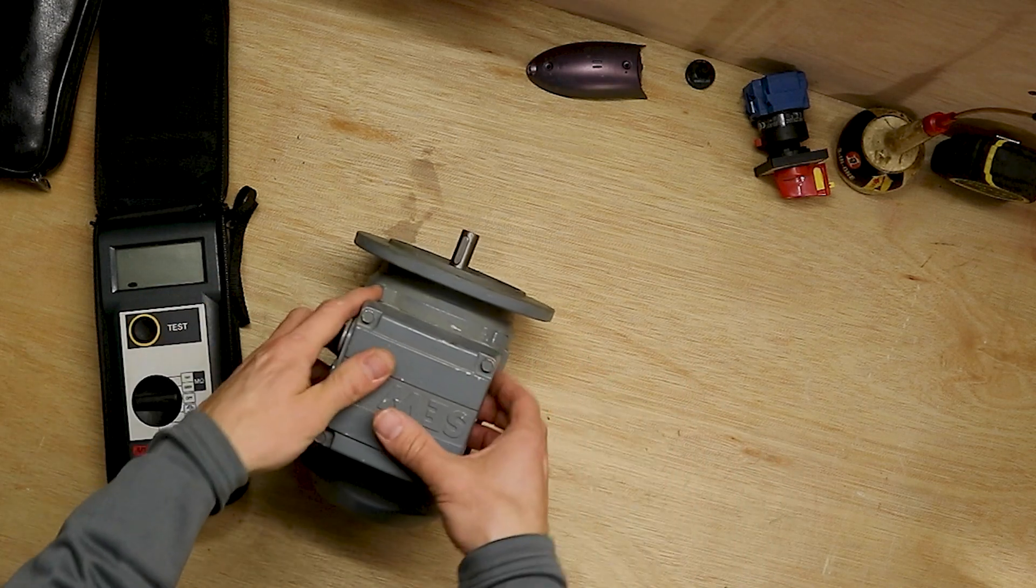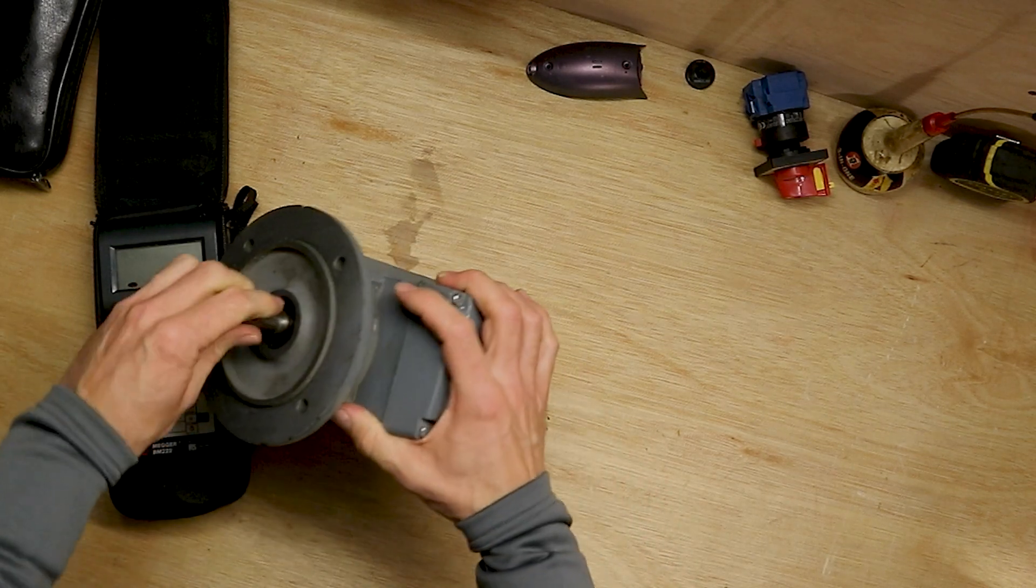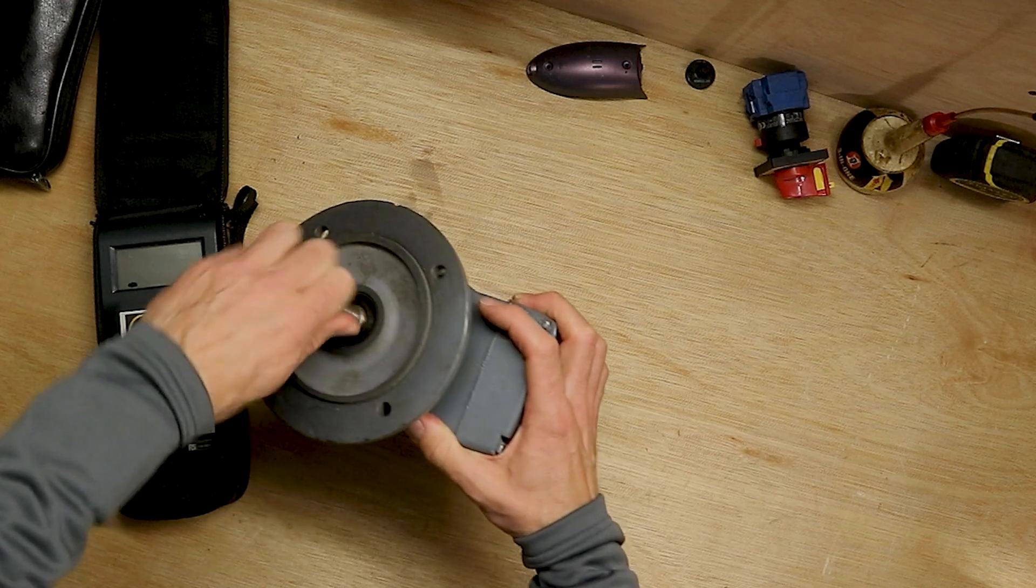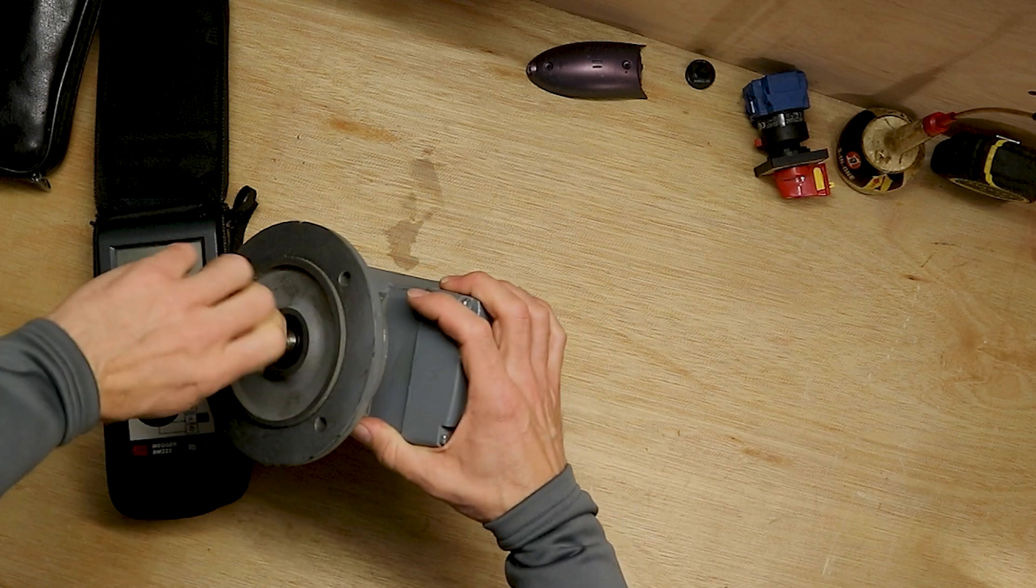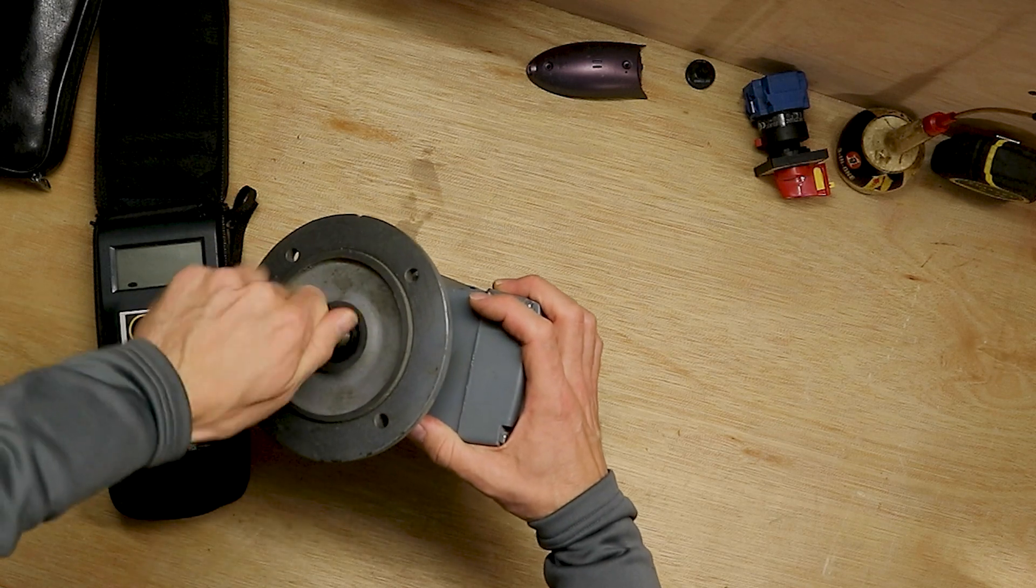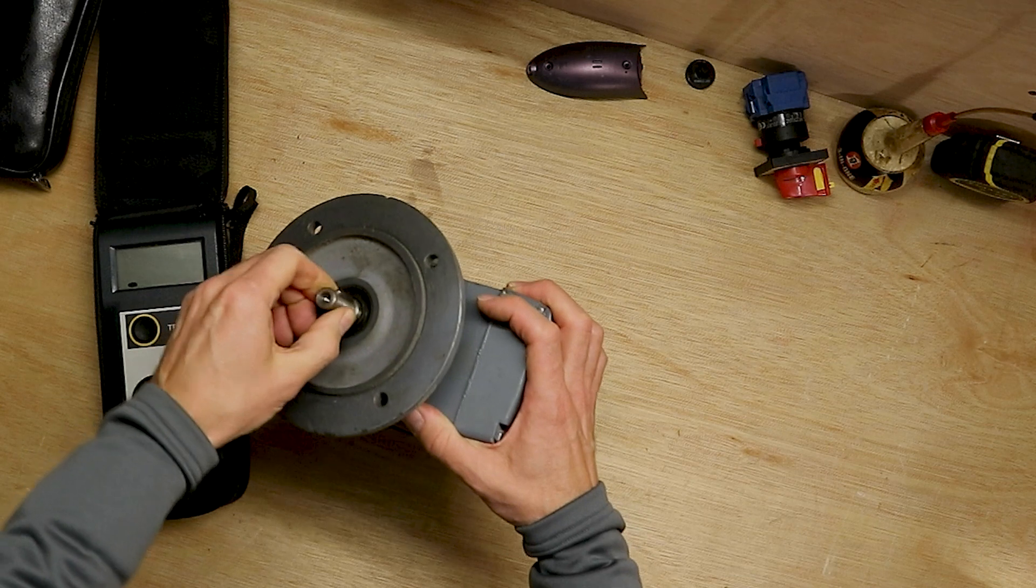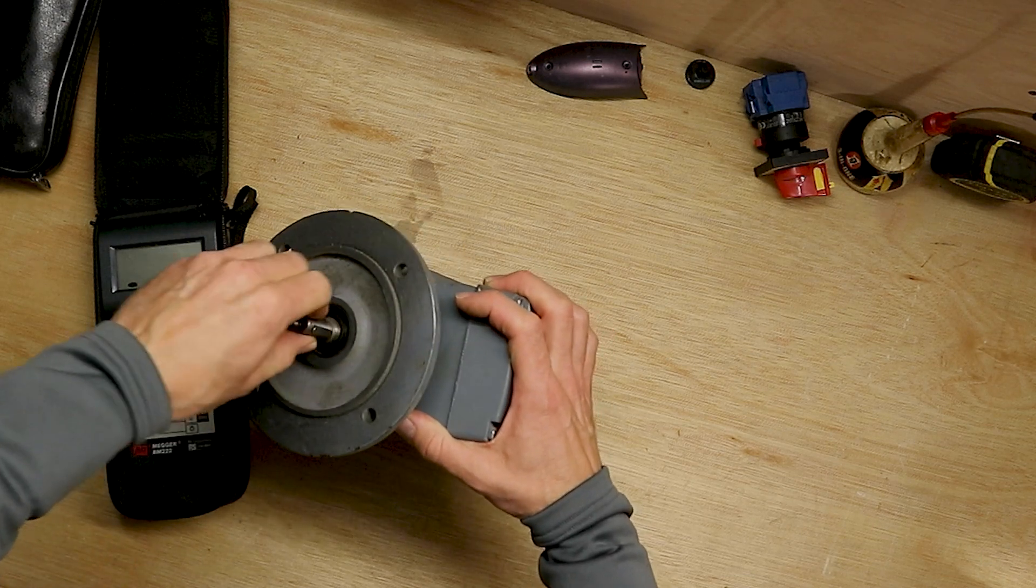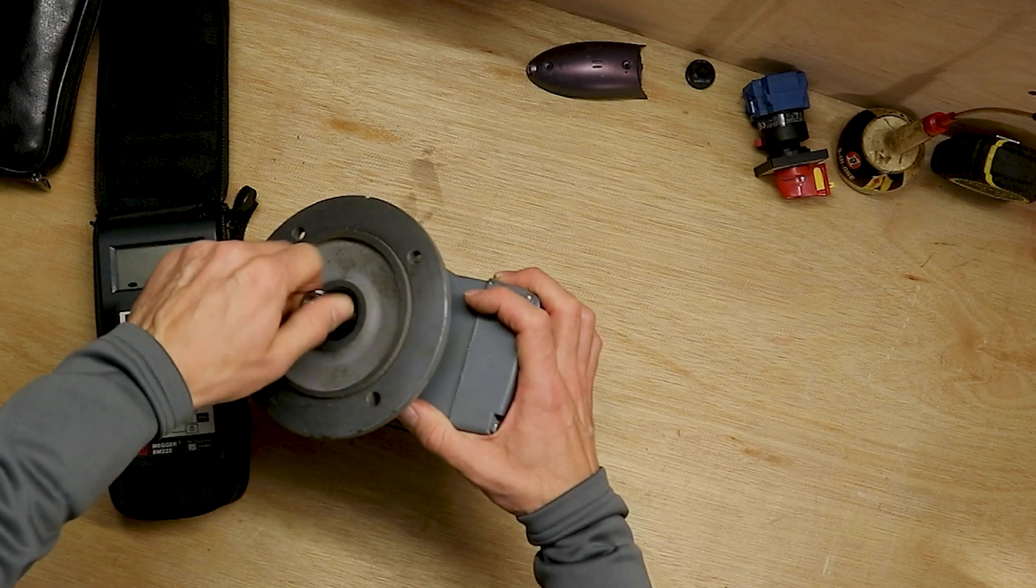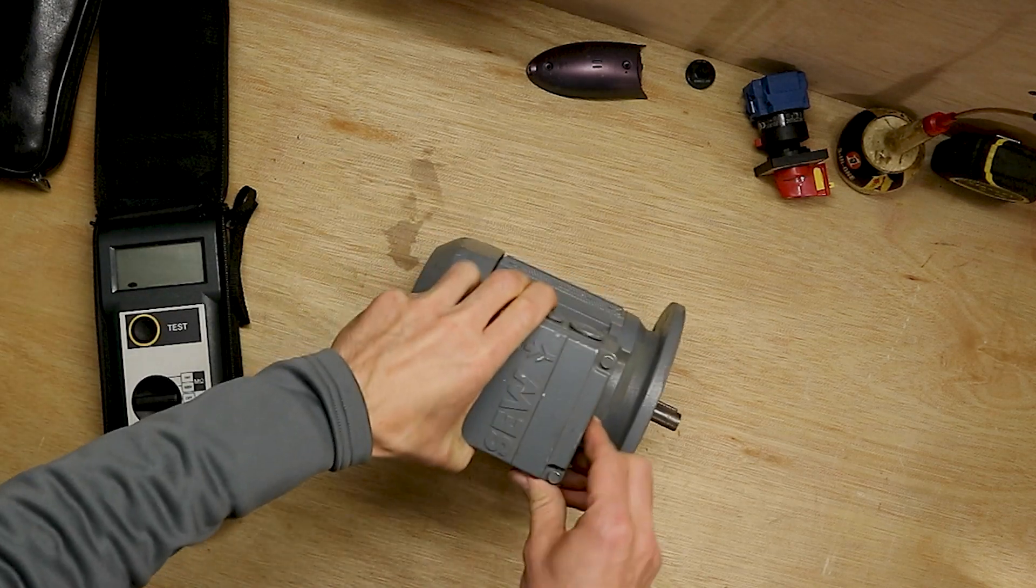One of the first tests that we can do is to check that the bearings are okay. We want to check any mechanical looseness here, any noise, any friction, any grumbling bearings, just some basic checks. Make sure it feels tight, it's not too loose, there's no noises in there, no grumbling. All feels good.